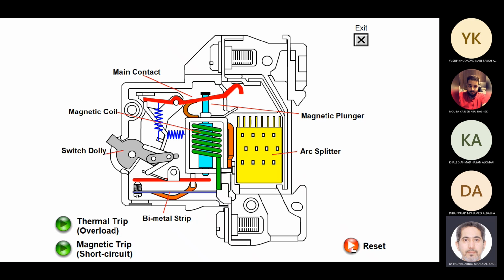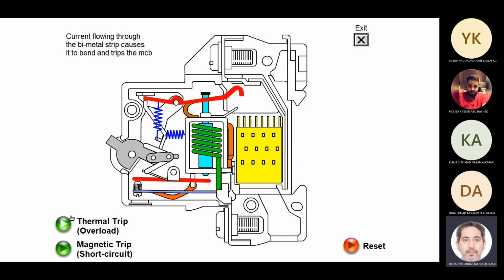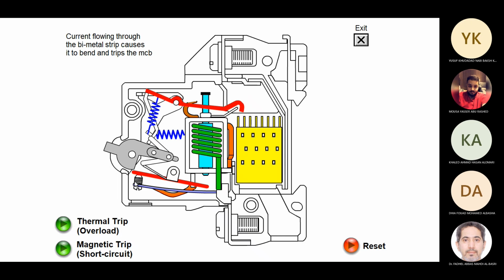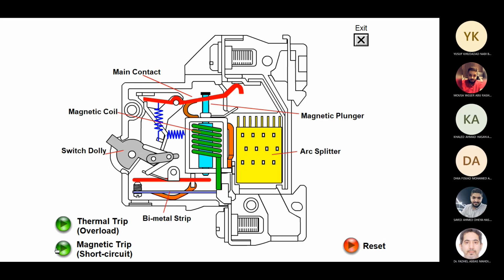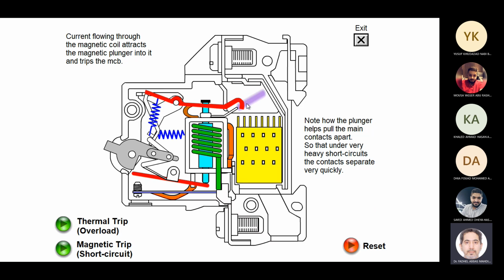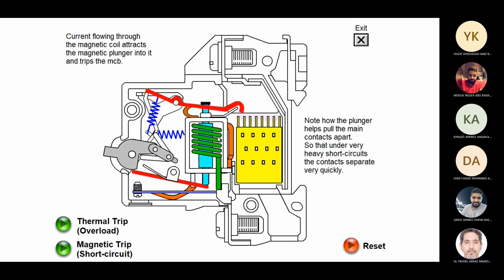And as a demo, I'll just show you here. Now, this is during, say, an overload condition where the current is small. As you can see, this is bending, and the breaker opens. However, during a short circuit, an arc is initiated and it is split somewhere here. And this is the basic principle of the breaker that we have at home, whether it is a molded case circuit breaker or a miniature circuit breaker. So this is a very important part, which is arc quenching.